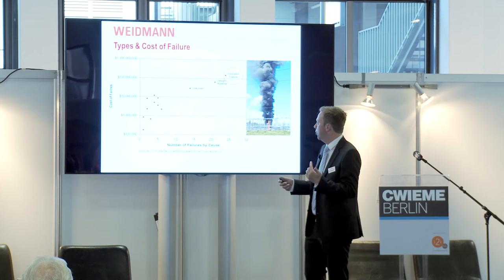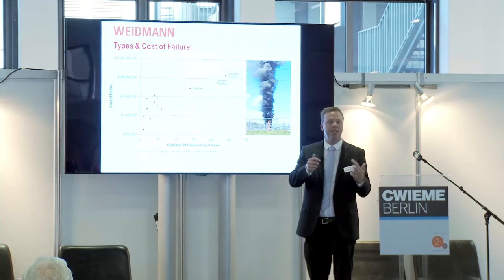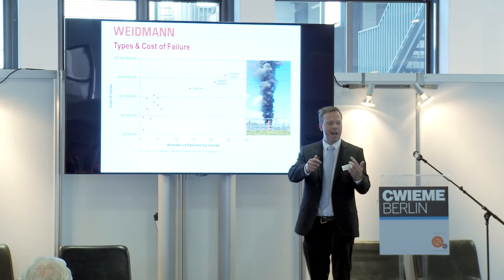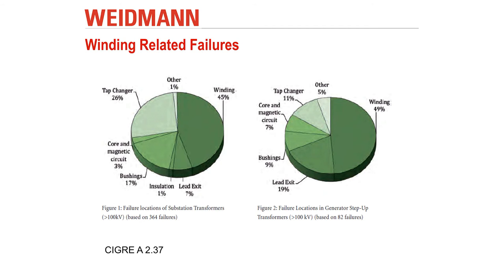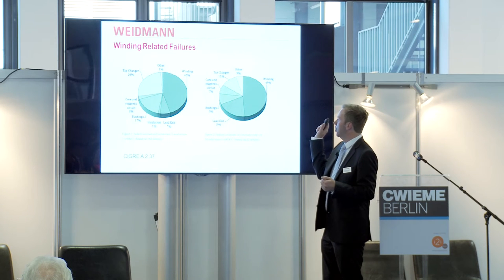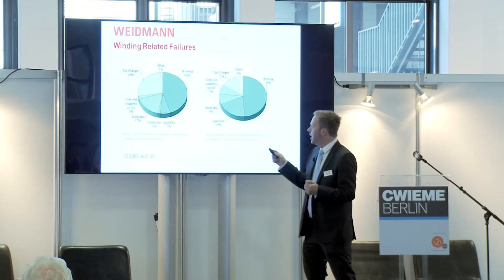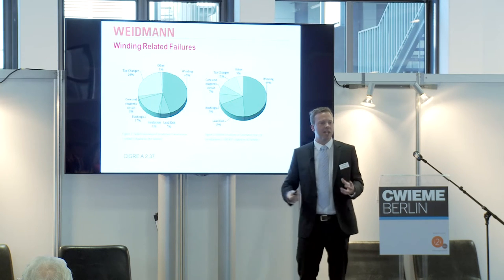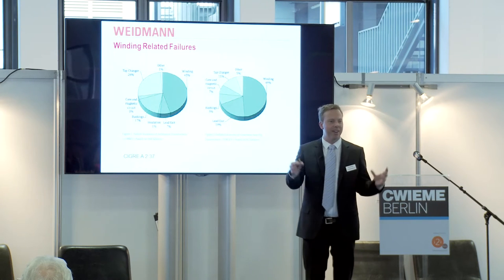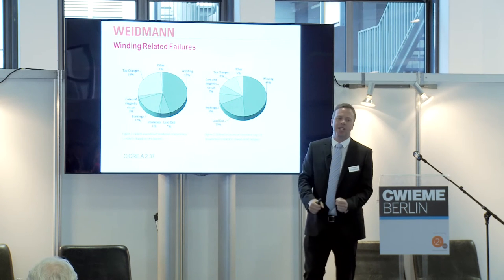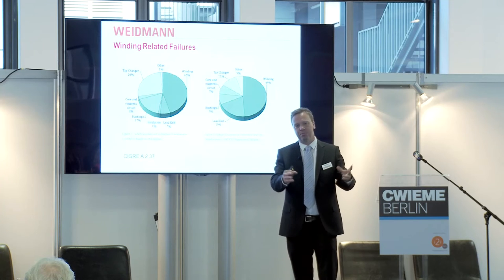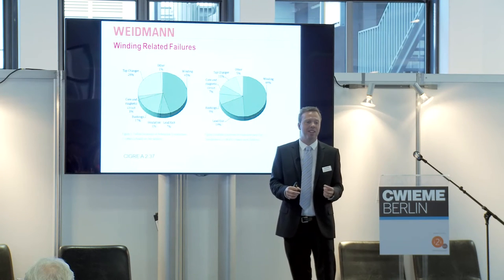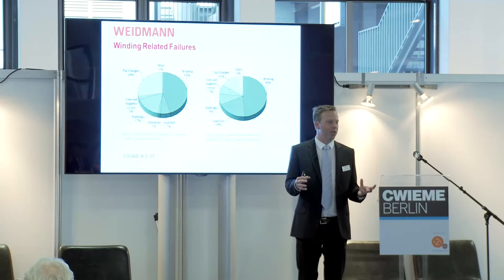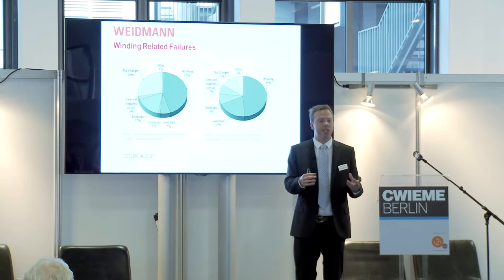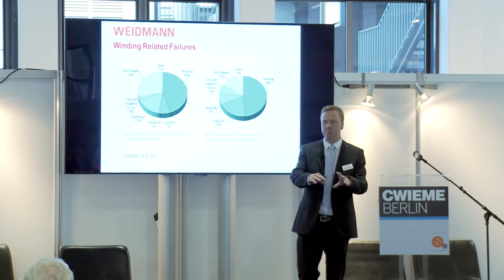That's the first thing to note. However, what this points to is that we need to be monitoring the insulation - we need to understand better what's happening to it. If we go a little deeper, we can see that the related failures are in the windings. So again, we're talking about the core of the transformer, inside the winding, looking at the insulation. This is moving towards an embedded solution of having sensors and technology embedded within the transformer insulation package.